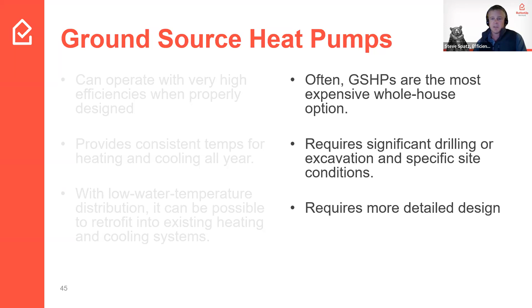So you have a lot of flexibility again with the ground source system, as you do with an air to water, about how you distribute that heat energy in the building. It can be hydronic, it can be forced air, it can be a variety of different distribution types. But again, it does have to be designed around the heating capacity of what the heat pump equipment can do. So it has to be low temperature design to make this work.